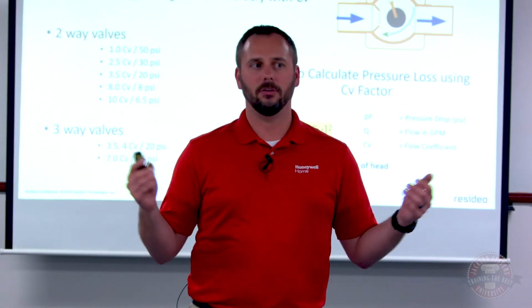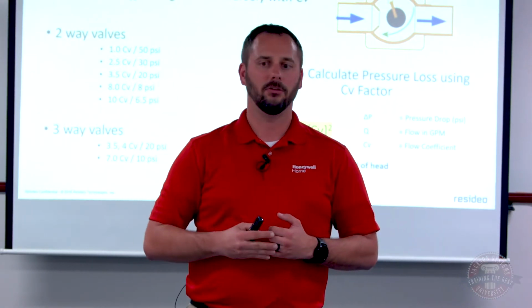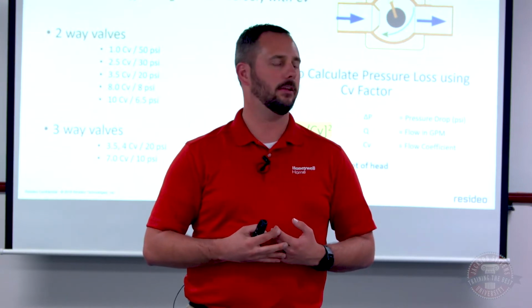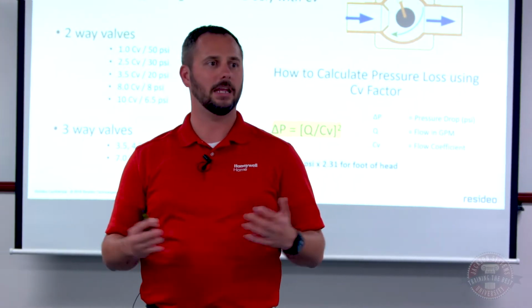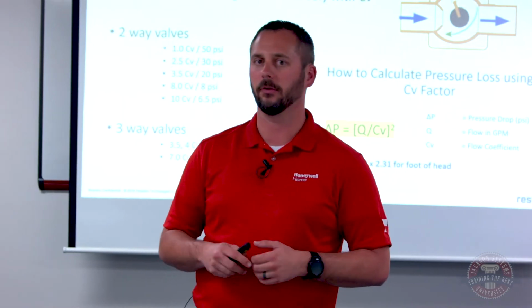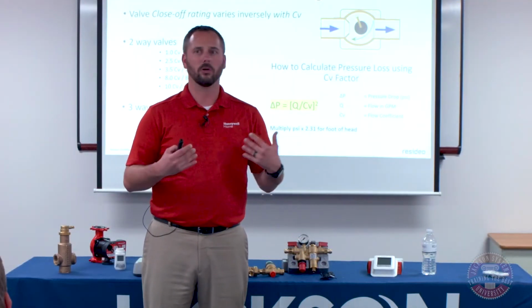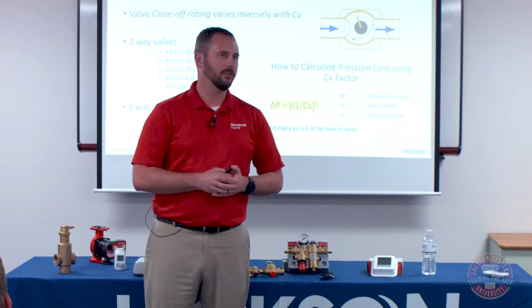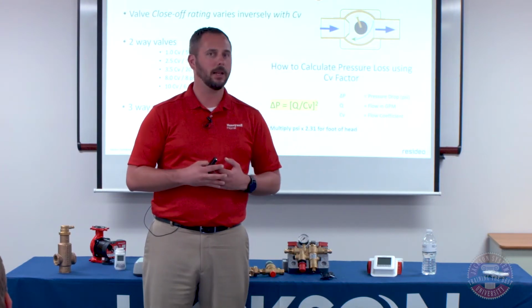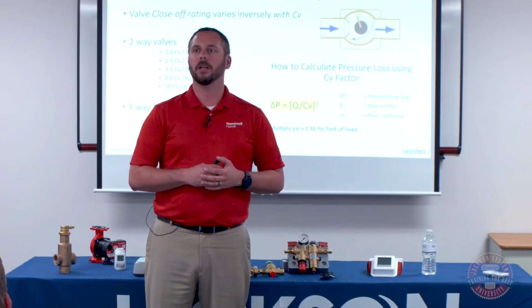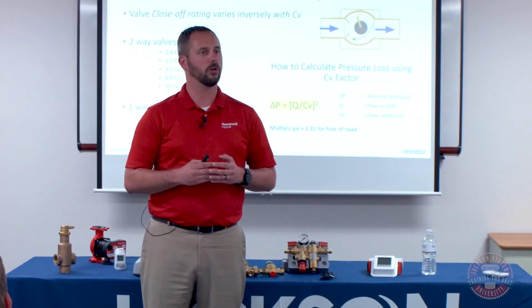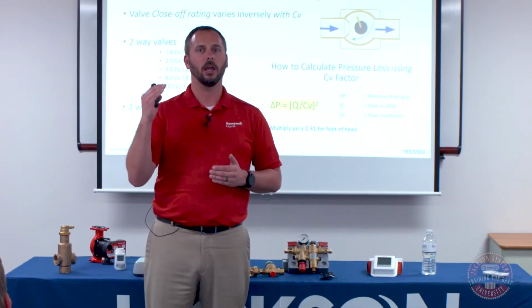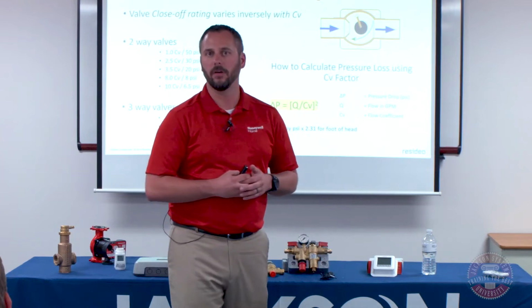In a hydronic system, you saw the pump sizing. Adding 2.3 feet of head is very rarely going to do anything with the sizing of the circulators in the system. So if you're doing a 1 1/4 system, I see it a lot of times with a 1 1/4 line that's driving, let's say 8, 9 gallons a minute, it's maybe going to add 3 feet of head. So you can easily take a 1 1/4 line in most instances and reduce it down to 1 inch for the valve.